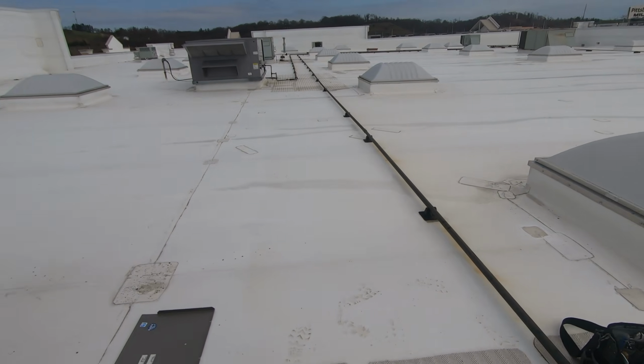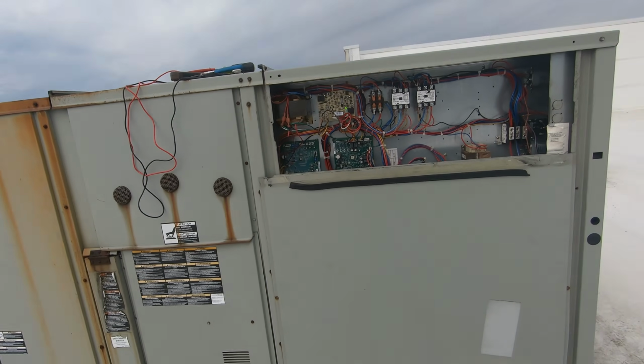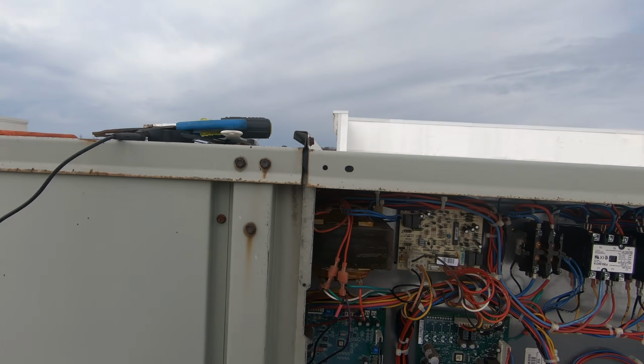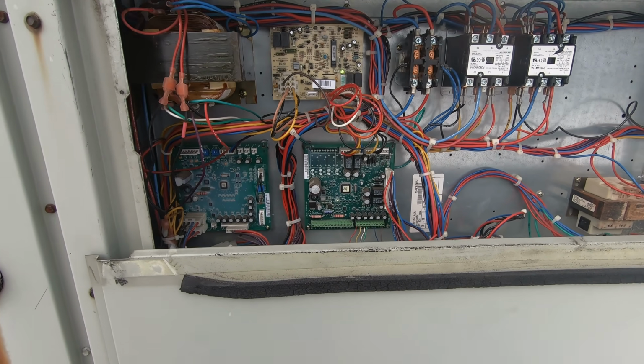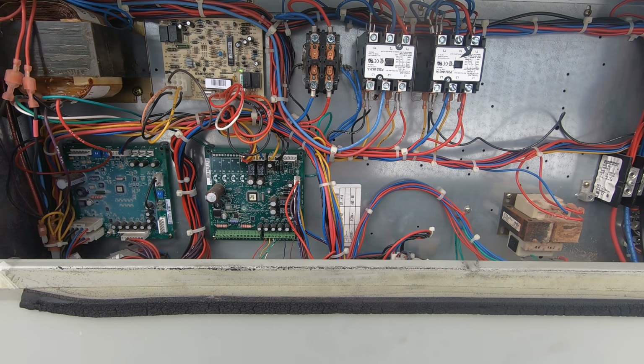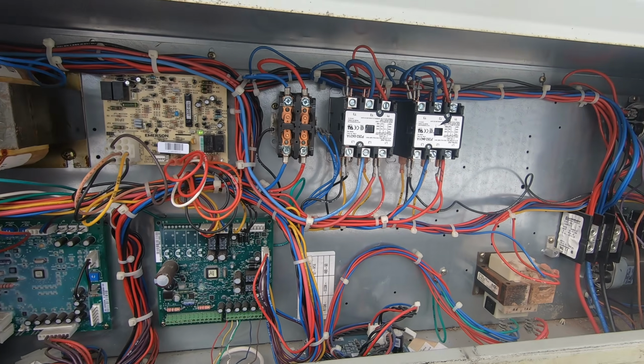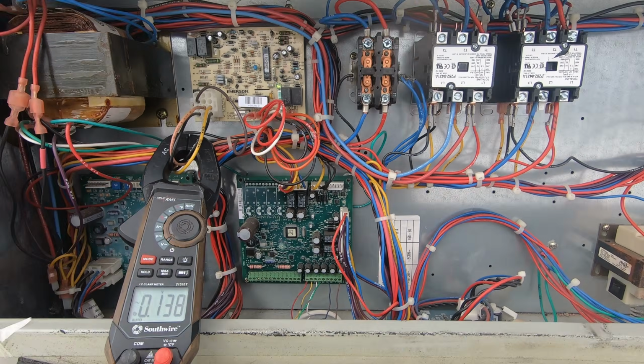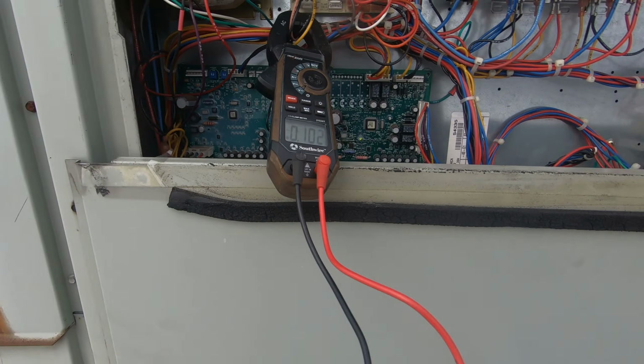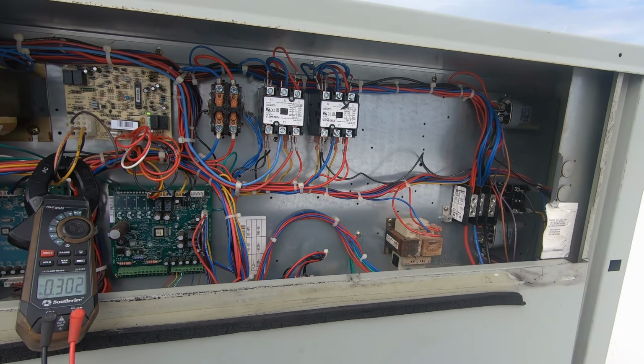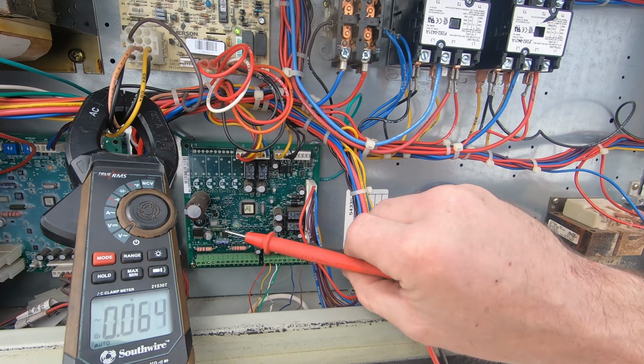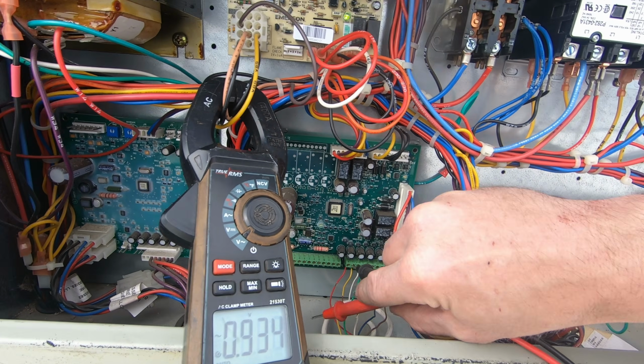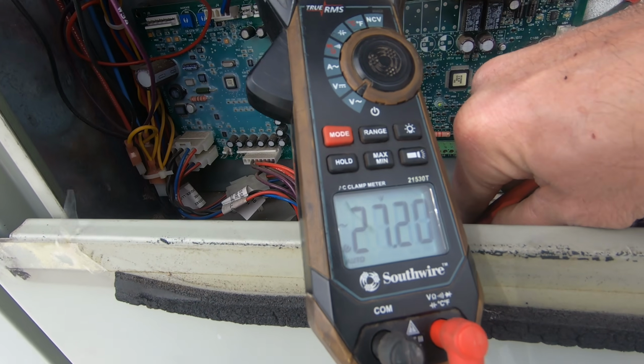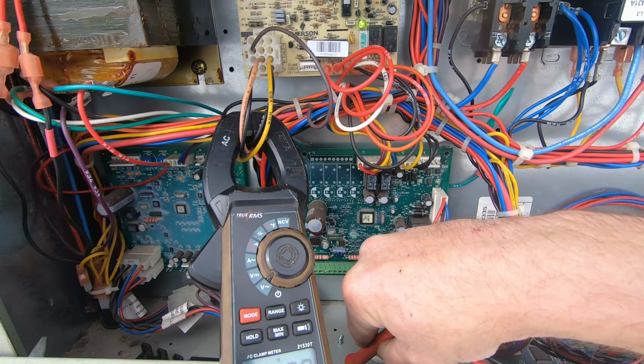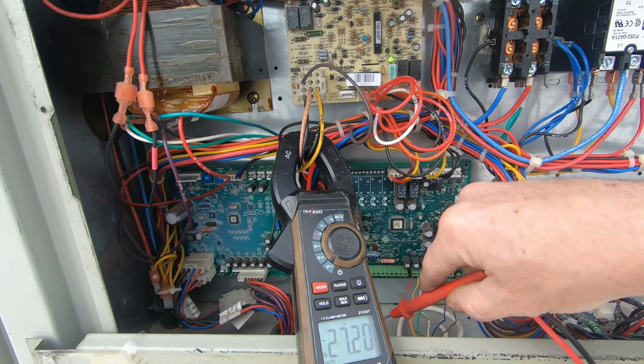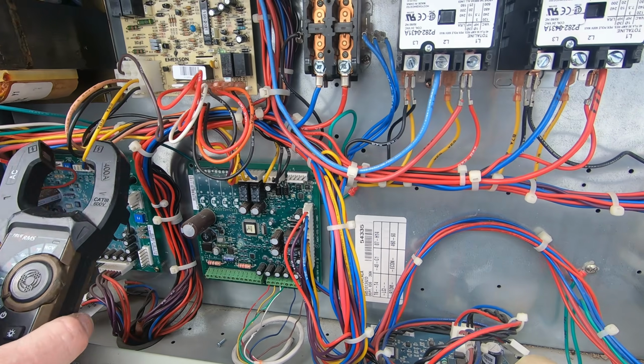Removed my jumper. It looks like we might still be calling for one stage of cooling. We confirm that with my meter. That would be good. Hopefully those remote sensors are connected when I get back after we restored 24 volts. They're the Honeywell ones. They're kind of a pain. You have to push the button. And in we're calling for first stage cooling. It is communicating. We're good to go on that.